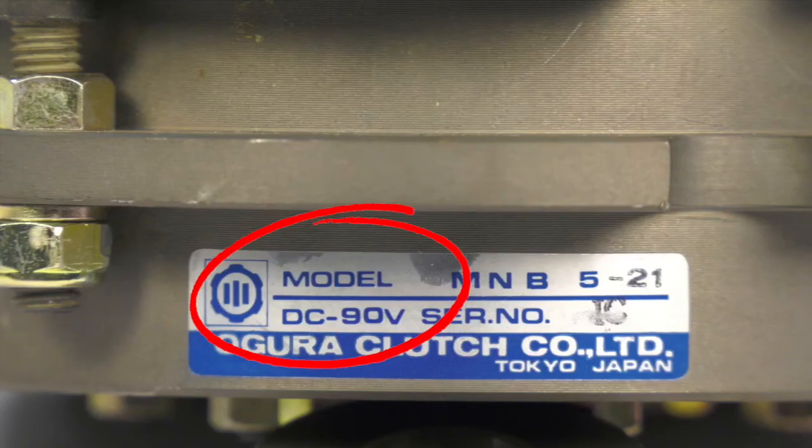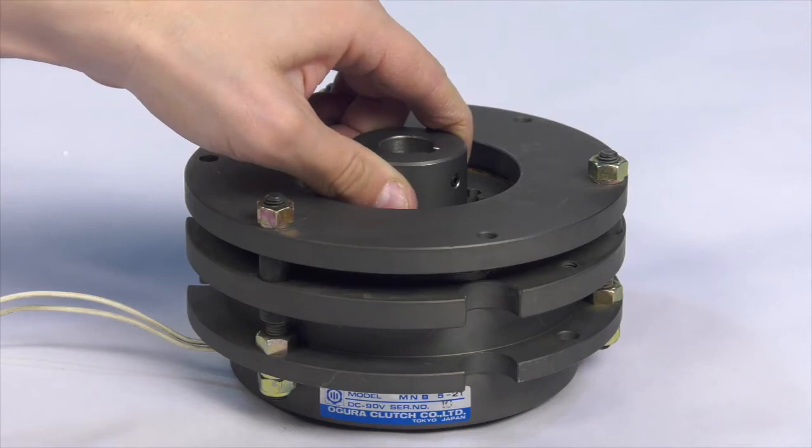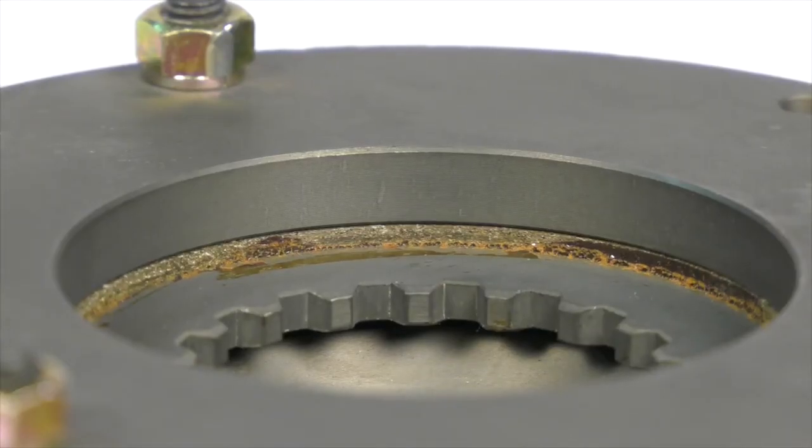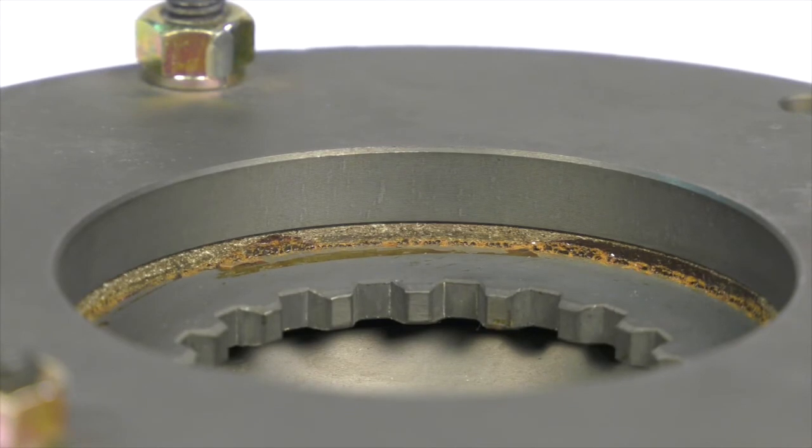So to reposition the friction disc, temporarily energize the brake coil at the rated voltage shown on the label and then slide the hub into the friction disc, which can be a spline or square depending upon brake model.